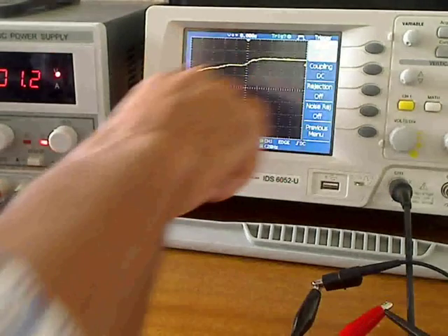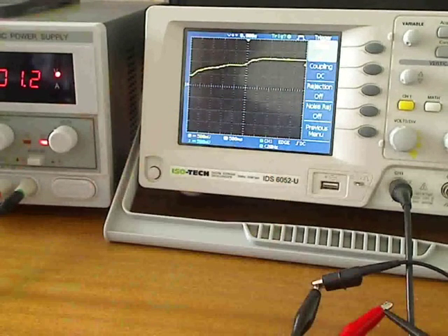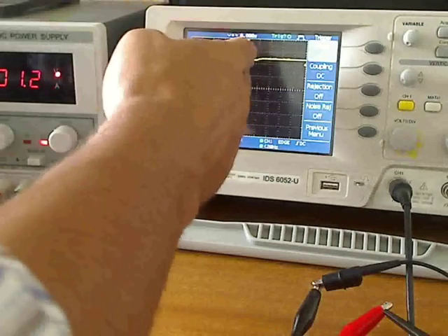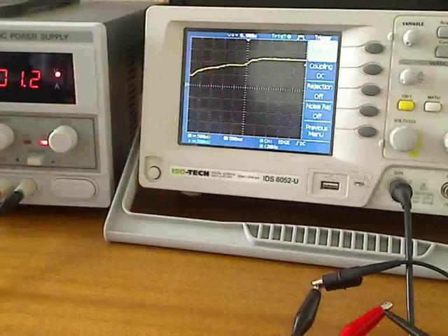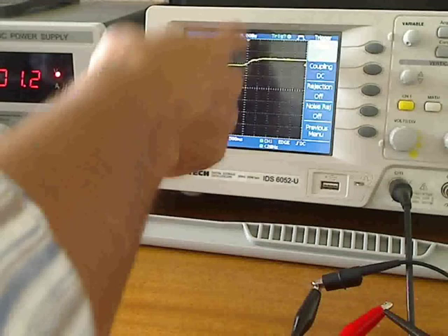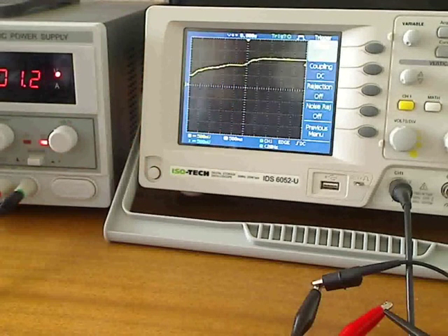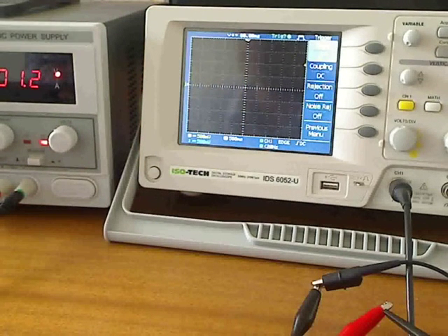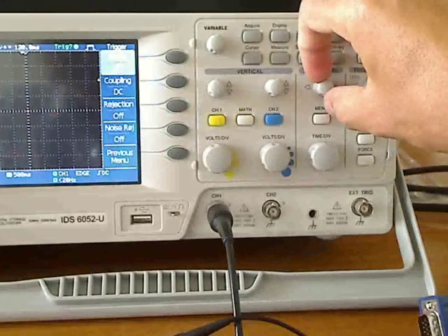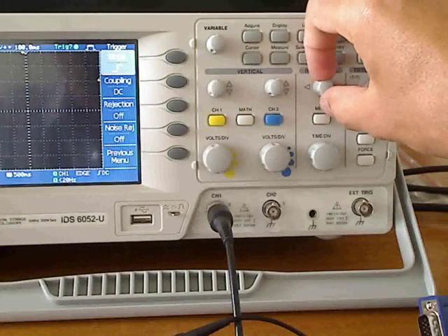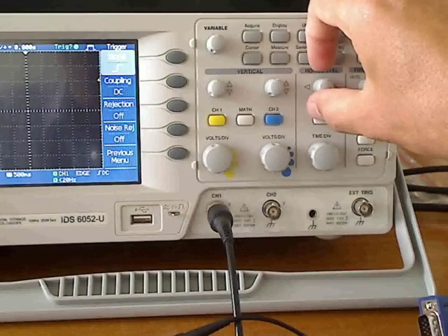And that's the 0 of the trigger. So it also stored the preceding 5 blocks, which is 2.5 seconds. So 2.5 seconds before it triggered, it also sampled, because I've set my trigger time in the middle. You can change that using that button there. But it makes sense to have it at 0. So you can see what happened preceding and after.